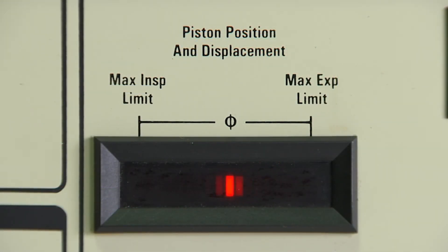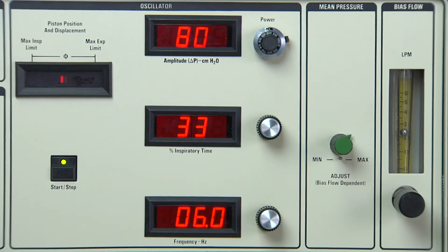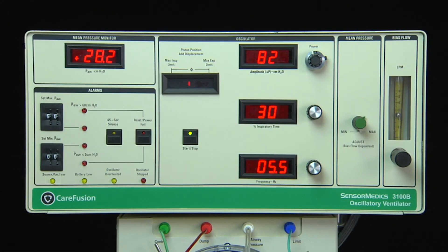The piston position and displacement indicator provides the operator with information on the position of the piston relative to its mechanical limits and the control settings. The 3100B features auto-centering and thus requires no intervention by the operator to maintain piston centering.